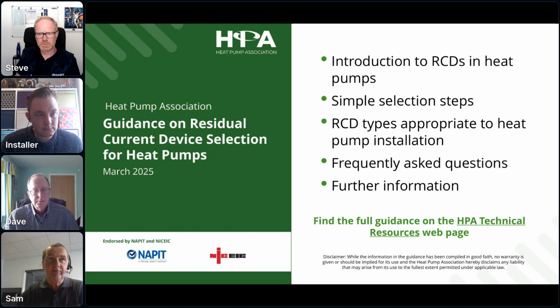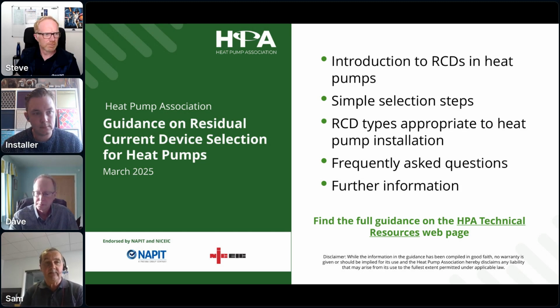And that comes in two forms. So firstly, each RCD has a nominal rating. So it's looking for an imbalance or a difference based on that nominal rating, whether that be 30 milliamps, 100 milliamps, 300 milliamps, 500 milliamps. And the reason for different ratings is because different items of equipment, different circumstances can generate that imbalance under normal operation, so not due to a fault.